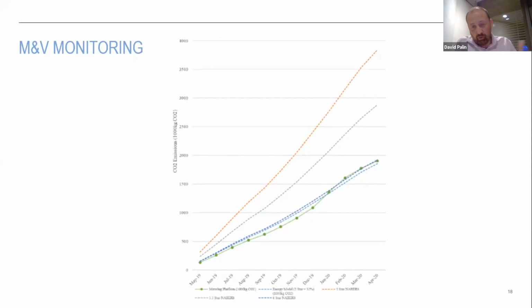What ARUP have done here is look at the top line, which I think is orange - that's a 5-star outcome. The next one down is a 5.5-star NABERS outcome. Next, one of the blue lines is 6-star, and then the actual model. The green line is actual performance. You can see we were a little bit under 6-star, with lower occupancy in the building to start with, then it moved up a bit, probably through gas, dehumidification, and summer loads. But it means we can actually see where we think we are at any point in time against what the model's saying.